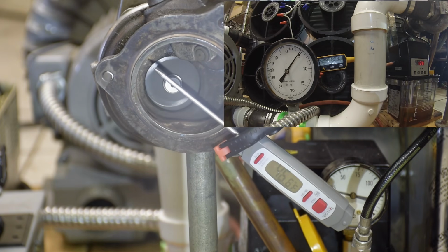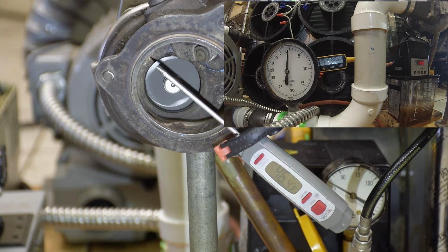But what might seem unusual to some viewers is that even though there's definitely increased output power, the temperature hasn't fallen by that much, but yet the fog coming out of the turbine has become much more dense. This is because the air cycle machine is removing water vapor from the air at constant temperature. Remember that latent heat is moved at a temperature that's constant. Sensible heat can be sensed by a thermometer, but latent heat, also known as hidden heat, is added or removed at constant temperature. So this is no surprise. The addition or removal of latent heat happens during a phase change, and in this particular case, the water vapor in the air is being converted from a vapor into a liquid.